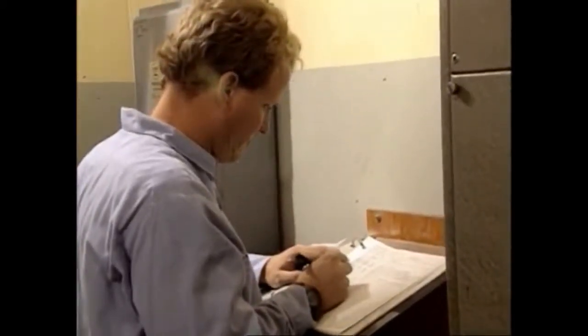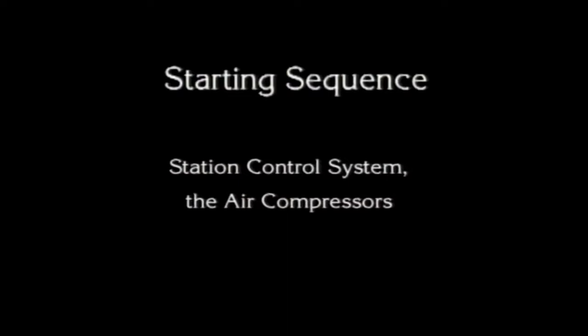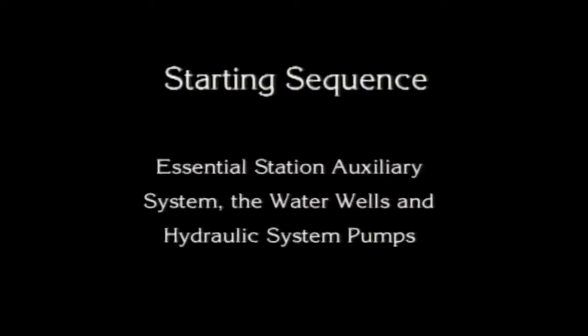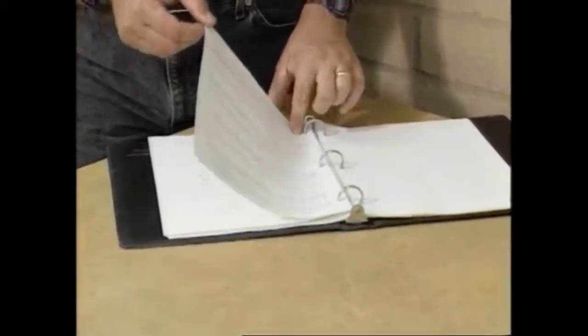The station book should describe the proper starting sequence for all of the station equipment. Here's a suggested starting sequence. Station lights, station ventilation equipment, start station sump pumps and listen for any unusual noise, station control system, the air compressors, essential station auxiliary system, the water wells and hydraulic system pumps, station last pump to start, station second pump, station lead pump, and all other station systems. As each piece of equipment is restored to service, it should be checked for proper operation, lubrication, and if appropriate, operating pressures and flow rates. The station book should indicate the operating ranges of the equipment.